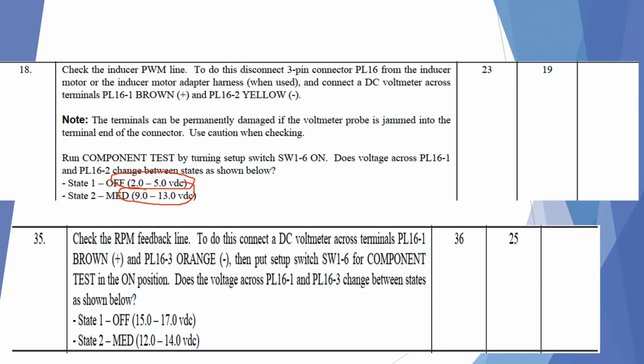on the motor. Another thing, with some ECM motors, you have an ECM RPM feedback line, which gives a feedback signal to the control board to tell the control board that the inducer motor has received the signal and it is running. So in this case, on the orange and brown wires going to the ECM motor, you should see 15 to 17 volts if the motor's off, and 12 to 14 volts DC if the motor is commanded to run. So again, these troubleshooting guides are very important to know the voltages that you should be seeing at these motors, to properly troubleshoot them, to see if the control board is sending these voltages out, if it's getting through the wiring harness and getting to the motor, or if the motor is getting the voltage but not running. So this will show you what the component is that you need to replace in order to get the inducer motor running again.